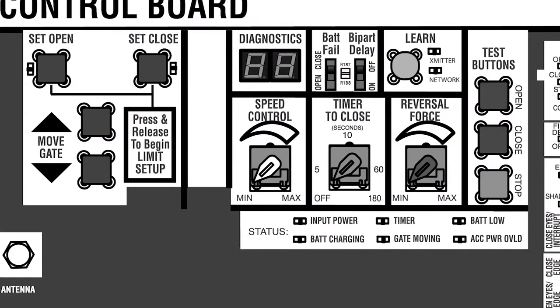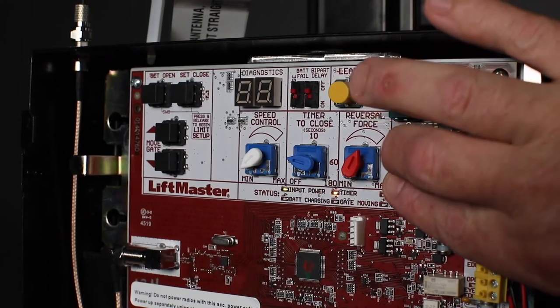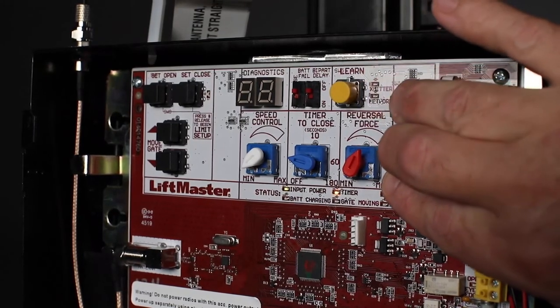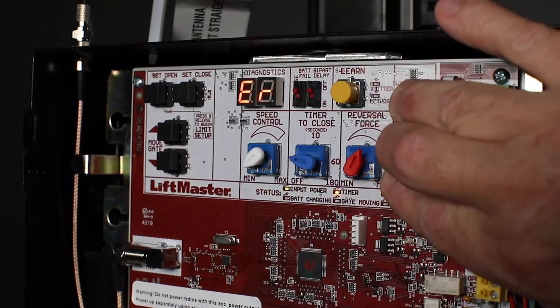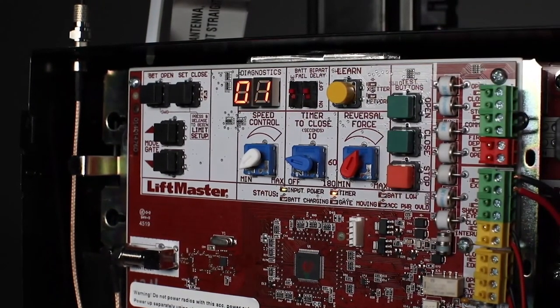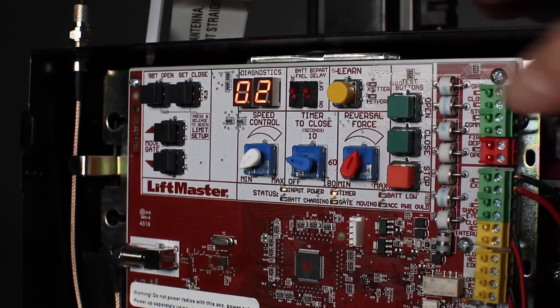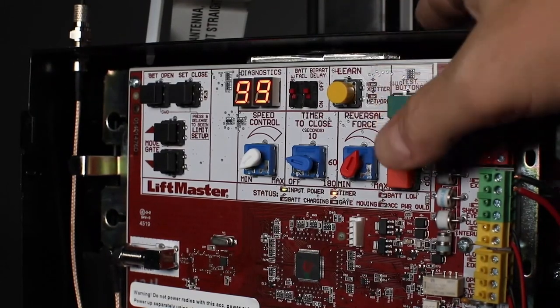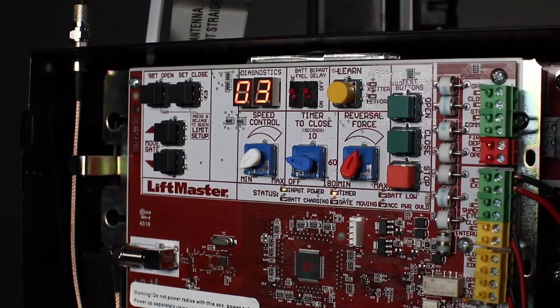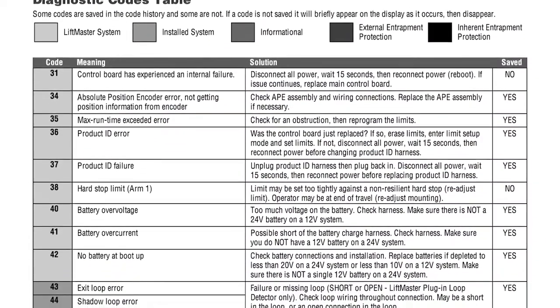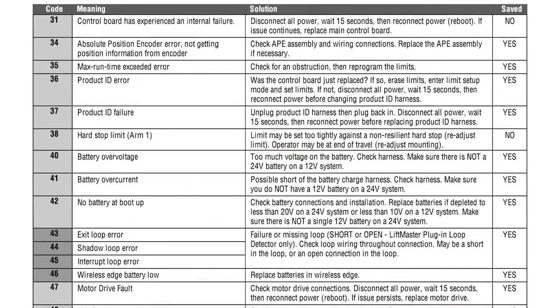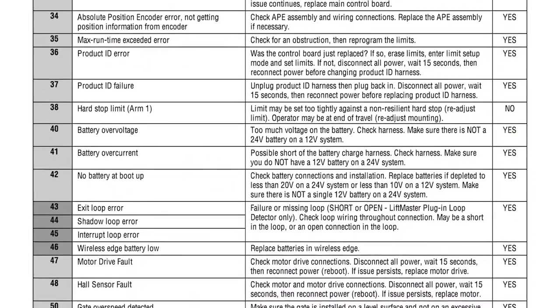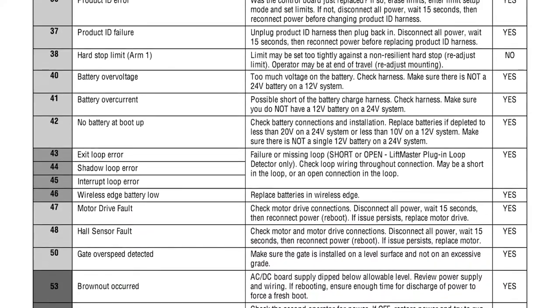The stop, close, and open buttons allow you to access and scroll through the diagnostic code history. A variety of error conditions are stored, allowing you to resolve these issues more quickly. A list of diagnostic codes can be found on the wiring diagram as well as in the manual.